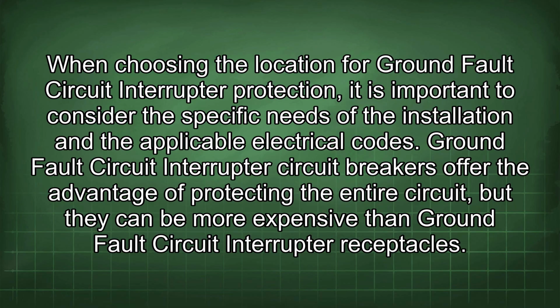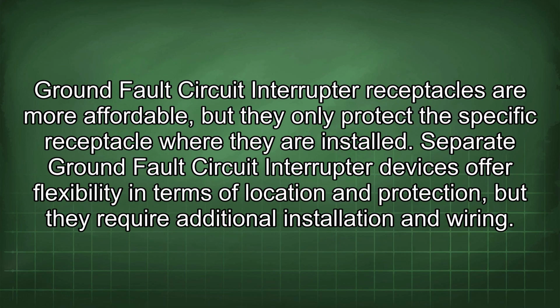When choosing the location for ground fault circuit interrupter protection, it is important to consider the specific needs of the installation and the applicable electrical codes. Ground fault circuit interrupter circuit breakers offer the advantage of protecting the entire circuit, but they can be more expensive than ground fault circuit interrupter receptacles. Ground fault circuit interrupter receptacles are more affordable, but they only protect the specific receptacle where they are installed. Separate ground fault circuit interrupter devices offer flexibility in terms of location and protection, but they require additional installation and wiring.